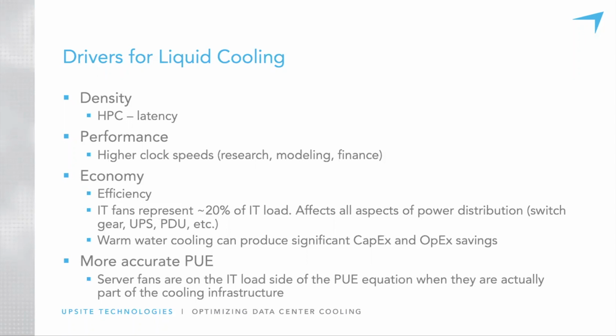And then one of the side benefits to liquid cooling is a more accurate PUE. As I mentioned, 20% of the IT load is actually fans, which should be considered part of the cooling load and not actually part of the IT compute load. So by removing the fans, the PUE equation becomes cleaner and more accurate. You're getting the IT compute load on one side of the equation, and you're getting the infrastructure load on the other side of the equation.